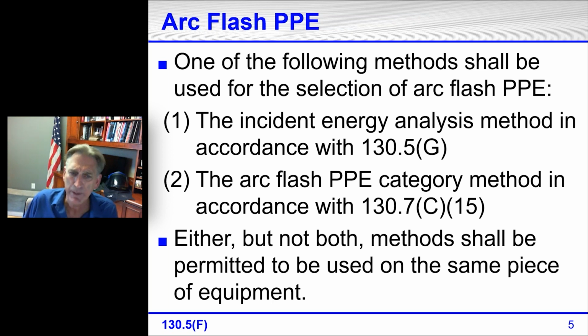Number two, the arc flash PPE category in accordance with 130.7C15. We're going to look at that one in this webinar. Either method is permitted, but not both on the same piece of equipment. In other words, if an electrician sees a label on the equipment and says, I don't like this arc flash boundary, I don't like the amount of incident energy shown on this label, I'm going to go to the table in 70E and see if I can get a lower category rating than what the label says, you can't do that. It's either one or the other.